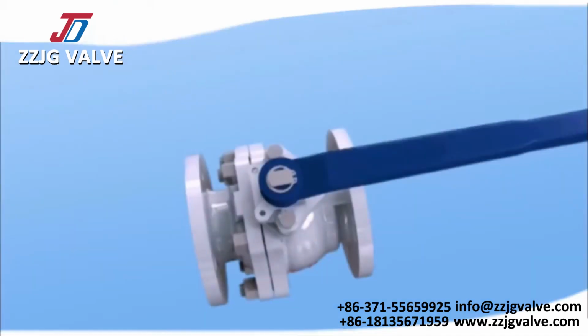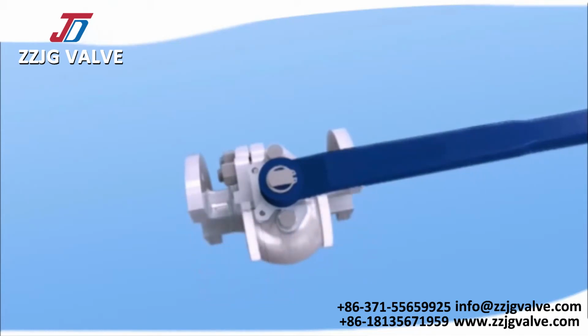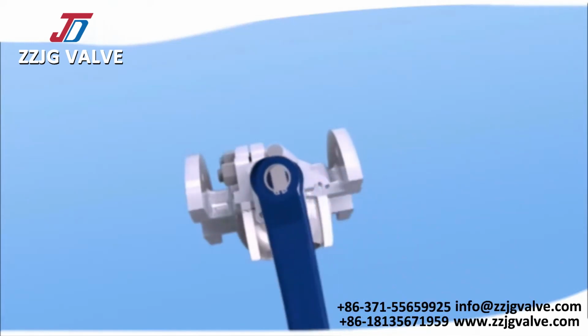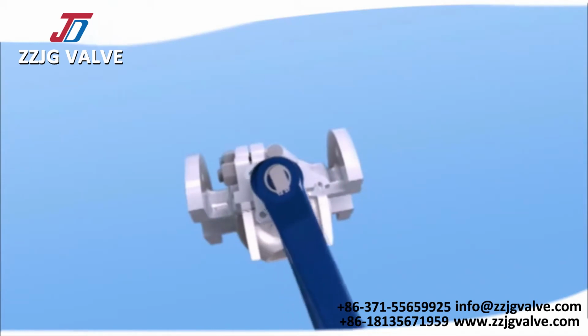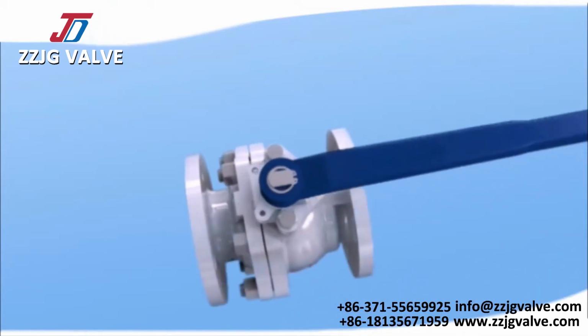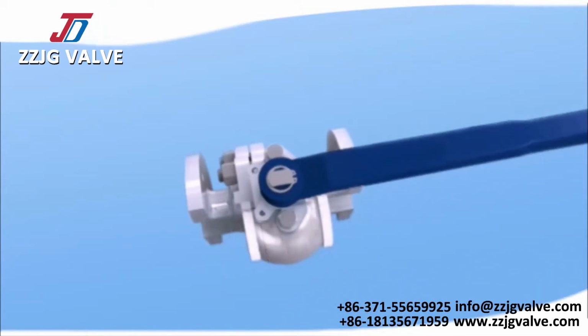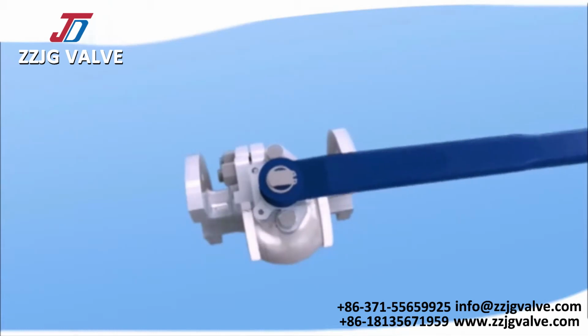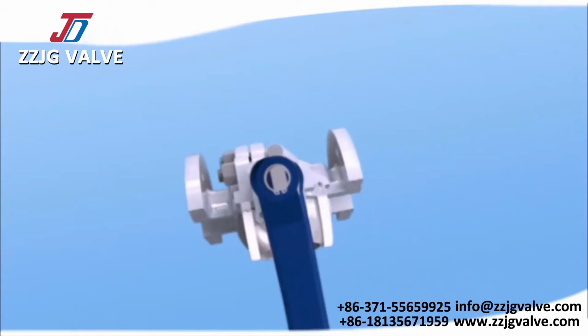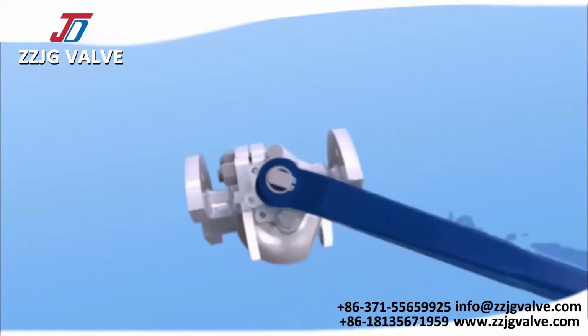The structure characteristics of floating ball valves made by ZZJG Valve are as follows. 1. Switch indication of the valve. The head of the stem is shaped flat, so it is easily distinguished whether the valve is in the on or off position. When the handle or stem flat is parallel with the pipe axis, the valve is in the on position. When the handle or stem flat is perpendicular to the pipe axis, the valve is in the off position.